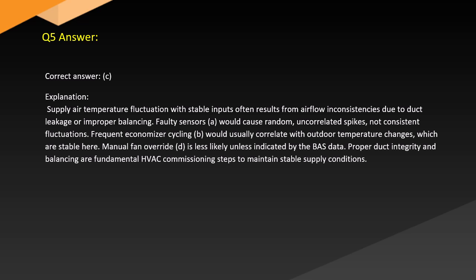Faulty sensors (A) would cause random uncorrelated spikes, not consistent fluctuations. Frequent economizer cycling (B) would usually correlate with outdoor temperature changes, which are stable here. Manual fan override (D) is less likely unless indicated by the data. Proper duct integrity and balancing are fundamental HVAC commissioning steps to maintain stable supply conditions.